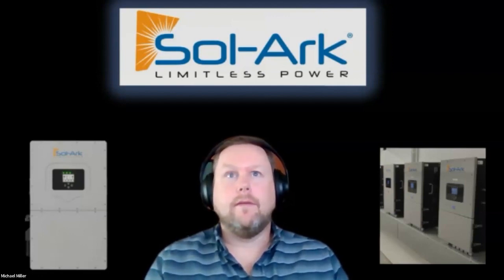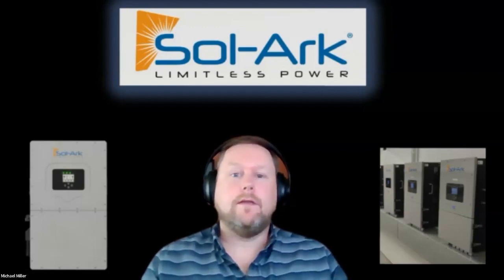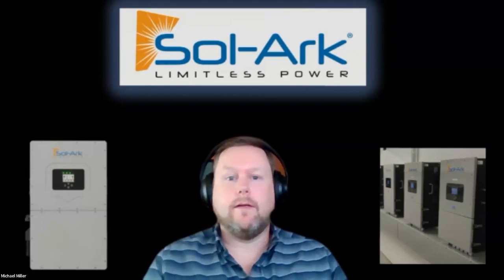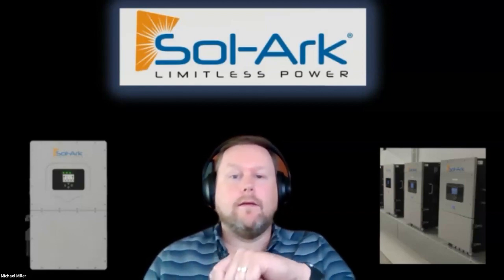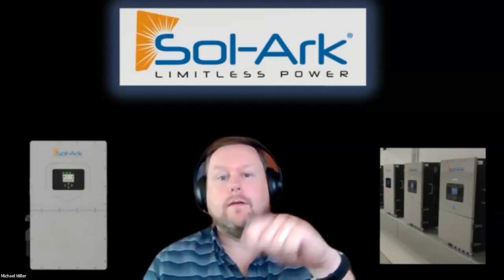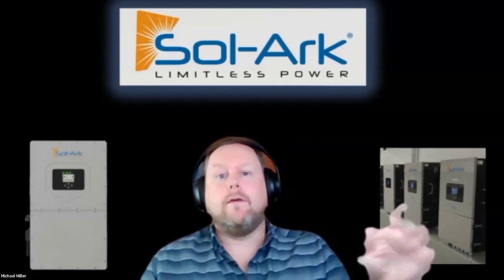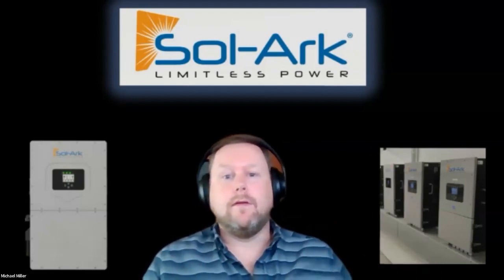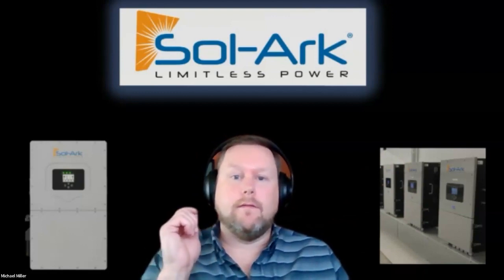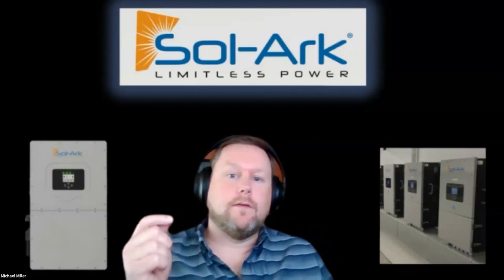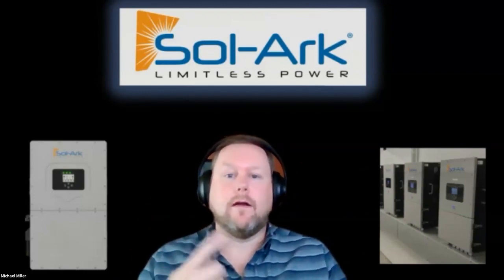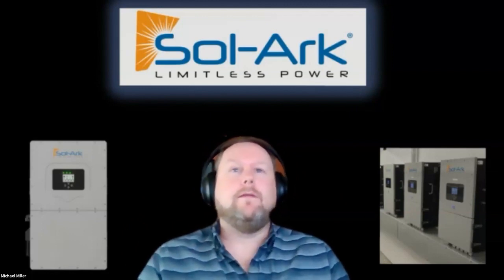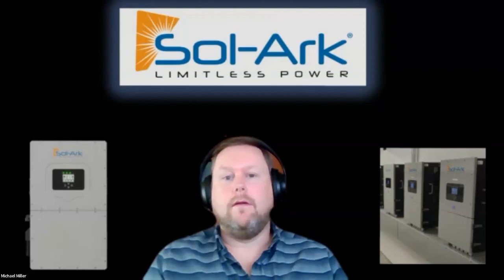How do you recommend doing an AC bypass switch? When I was up here in Michigan doing installs, I was putting those in. Essentially what we would do is come off the meter to the double throw switch if it's a 15K, it's 200 amp rated. We'd do a tap on the grid side of that switch, grid feed at the top, and then go to our 200 amp fuse disconnect to the grid input, and then connect the load panel. The panel you're going to back up connects to the center of the double throw switch, and on the bottom we'd connect the Sol-Ark output from the load side. I think we did bond it in that transfer switch, from what I recall.